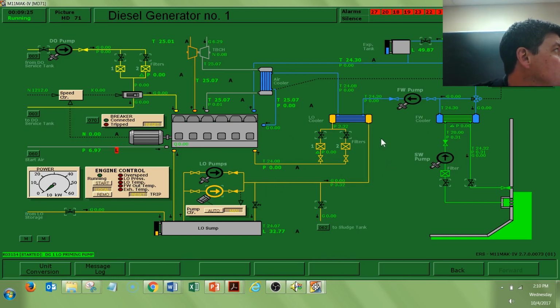I got my pump on, and I've got a pathway through here, and now I've got flow of lube oil. I'm also going to have some cooling water pathways. I've got this temperature controller. If you see what happens with the temperature controller, I have it manually set to 0, and the pathway for this cooling water goes through this cooler and then will make its way eventually to the engine. That one likely we would want to put into auto mode, which is going to allow it to warm up instead of having all of the flow cooled. So I'll put them into auto mode.